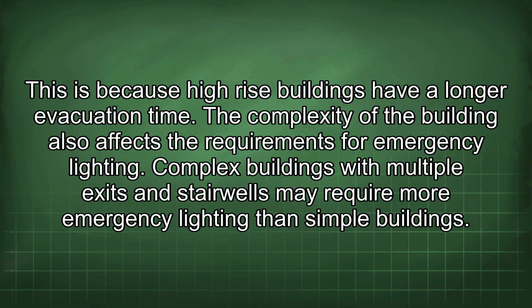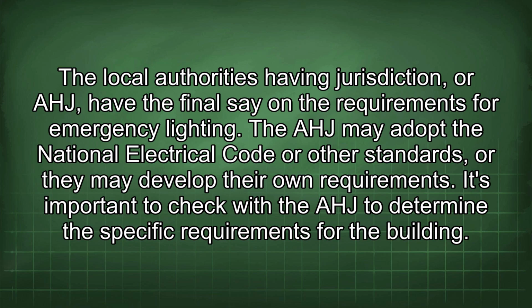The complexity of the building also affects the requirements for emergency lighting. Complex buildings with multiple exits and stairwells may require more emergency lighting than simple buildings. The local authorities having jurisdiction, or AHJ, have the final say on the requirements for emergency lighting. The AHJ may adopt the National Electrical Code or other standards, or they may develop their own requirements. It's important to check with the AHJ to determine the specific requirements for the building.